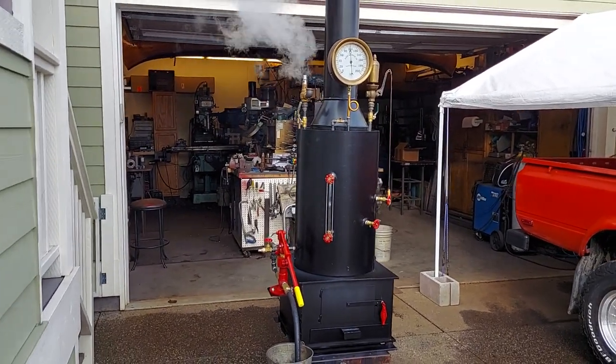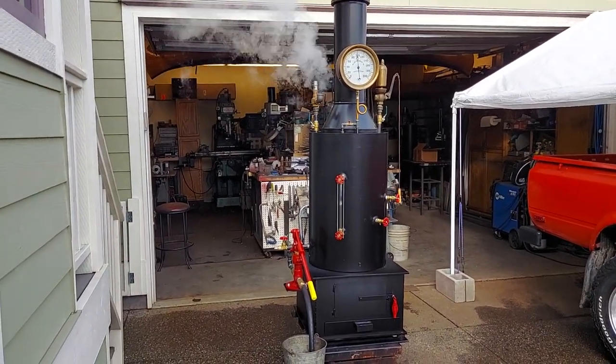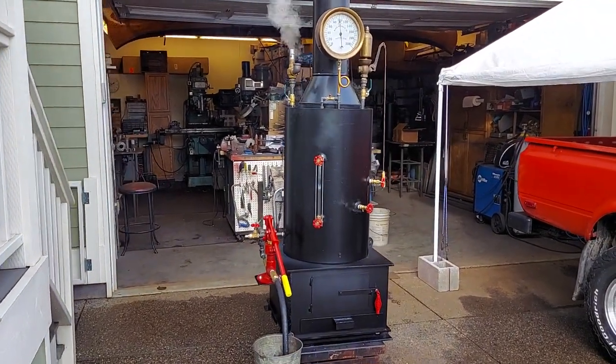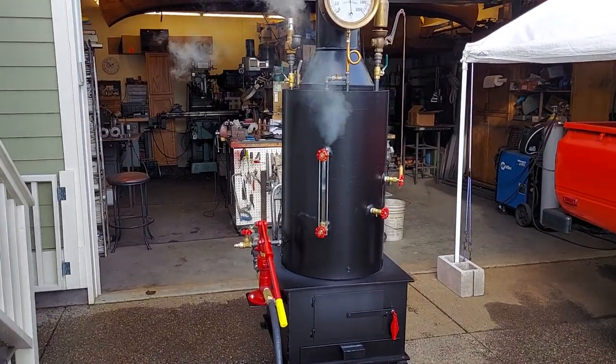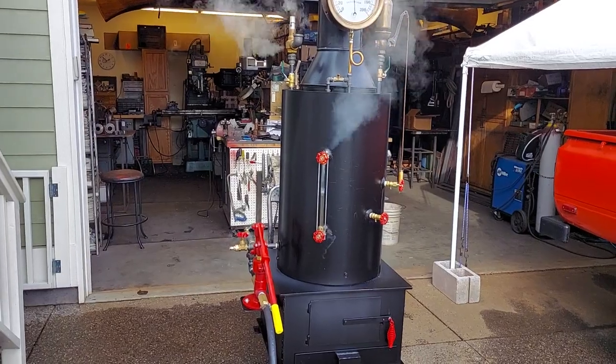Alright, here's my next boiler. The pop-off valve is going off at 100 pounds. The boiler itself is 20 inch diameter with 2 inch and a half copper tubes rolled in.